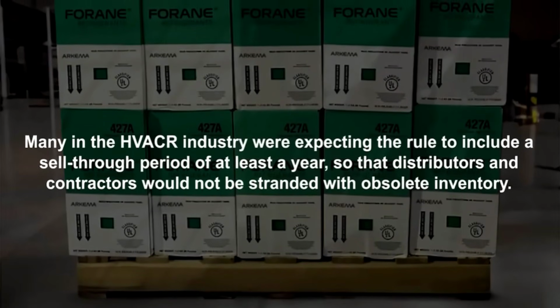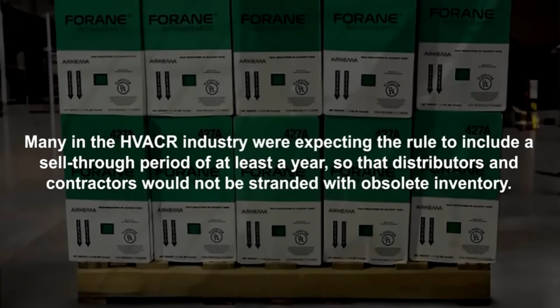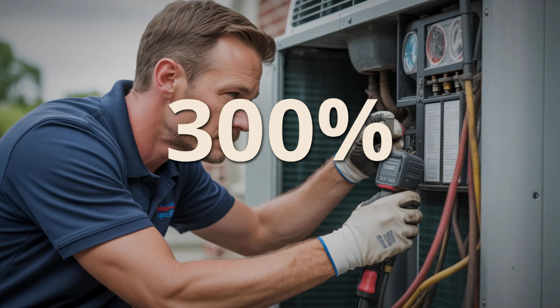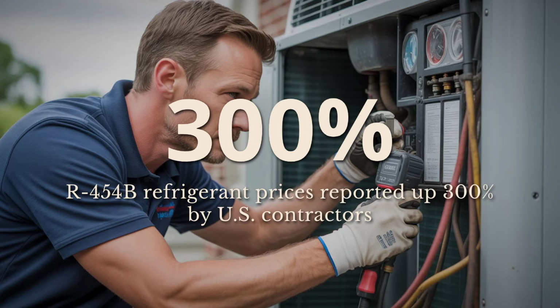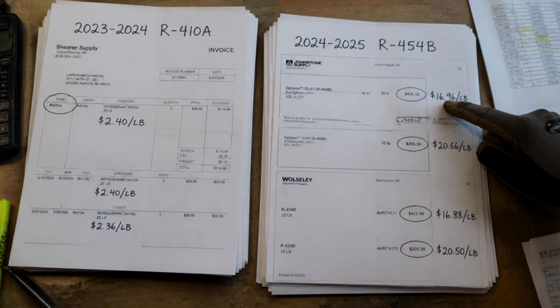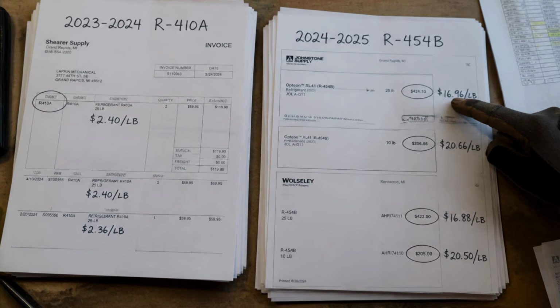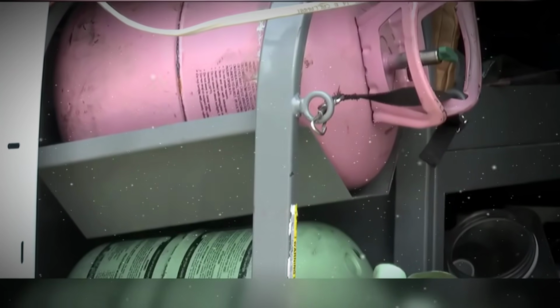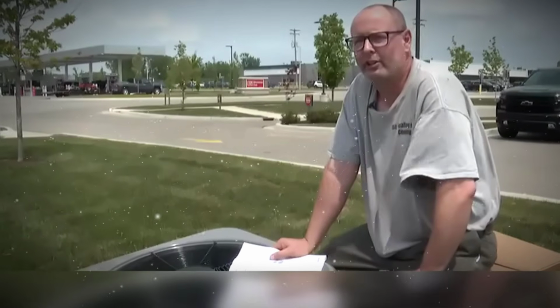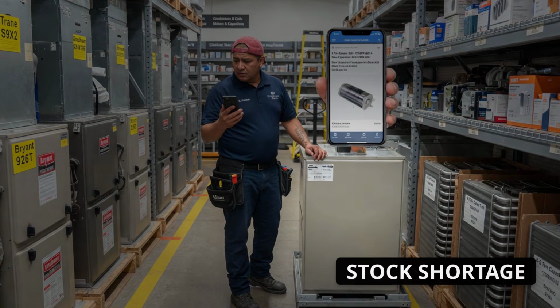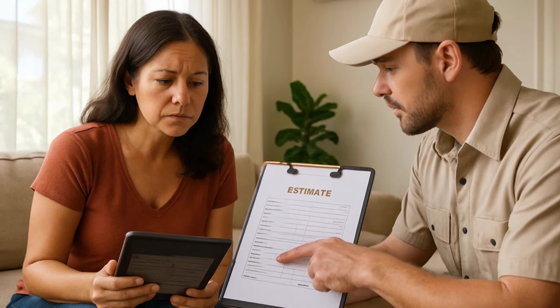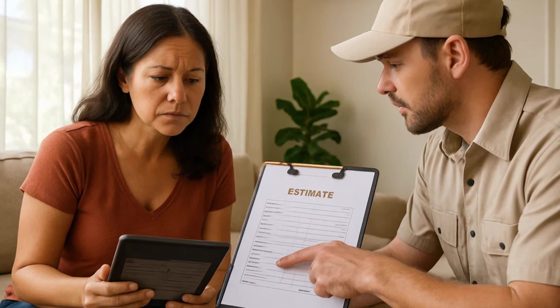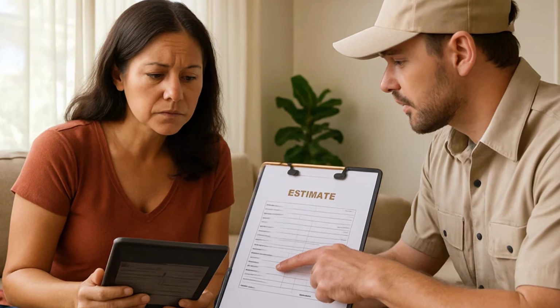The R454B supply chain has already proven volatile. Contractors in multiple states report refrigerant price increases exceeding 300% compared to what they were paying for R410A just 12 months earlier. Some technicians are stockpiling R410A in bulk to service existing systems because the replacement compound is either unavailable from their distributor or priced at a level that makes routine service calls uneconomical for the homeowner.